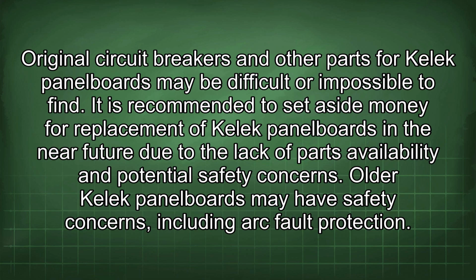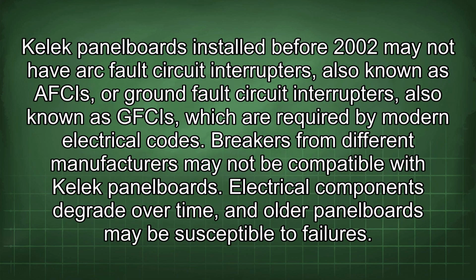It is recommended to set aside money for replacement of Kelek panelboards in the near future due to the lack of parts availability and potential safety concerns. Older Kelek panelboards may have safety concerns, including arc fault protection. Kelek panelboards installed before 2002 may not have arc fault circuit interrupters, also known as AFCIs, or ground fault circuit interrupters, also known as GFCIs, which are required by modern electrical codes.